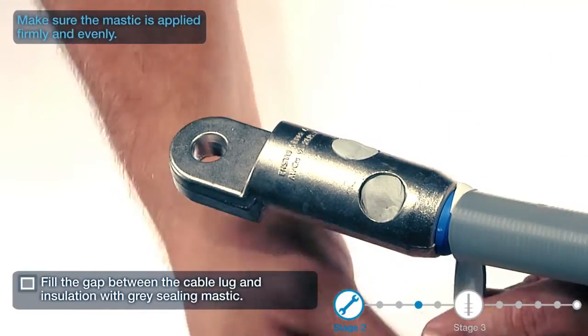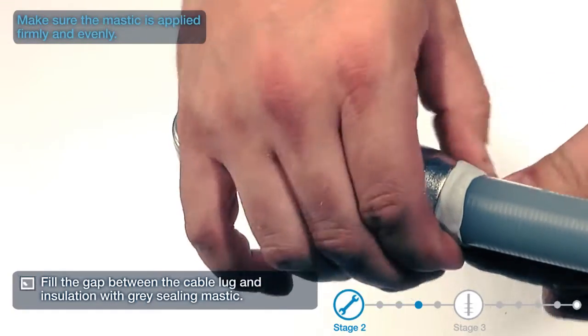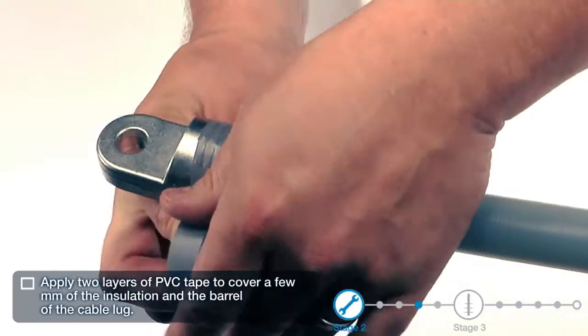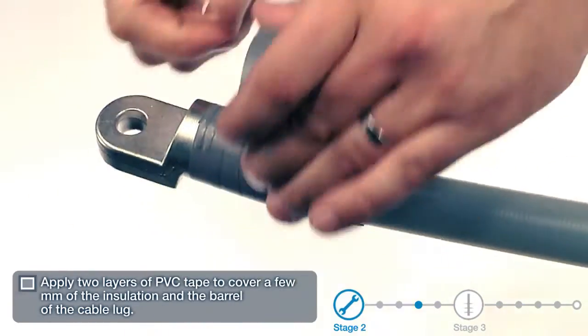Fill the gap between the cable lug and insulation with grey sealing mastic. Apply two layers of PVC tape to cover a few millimeters of the insulation and the barrel of the cable lug.